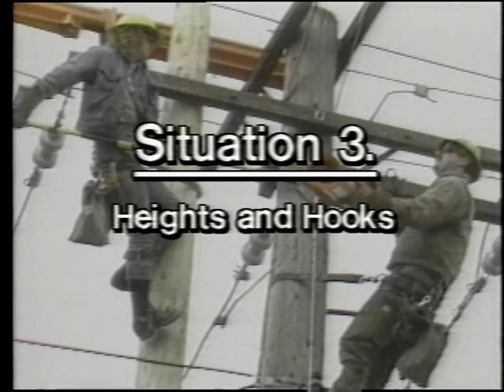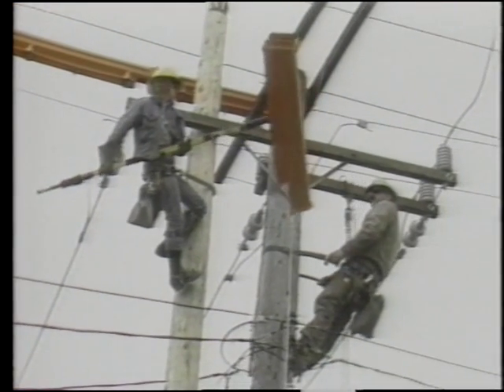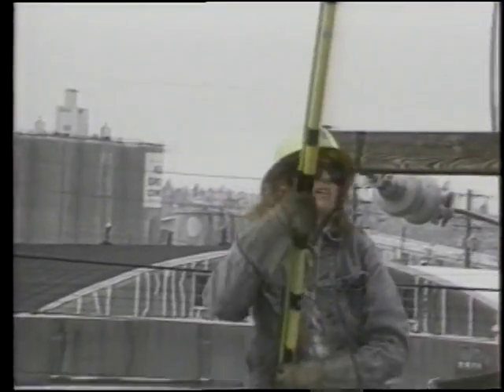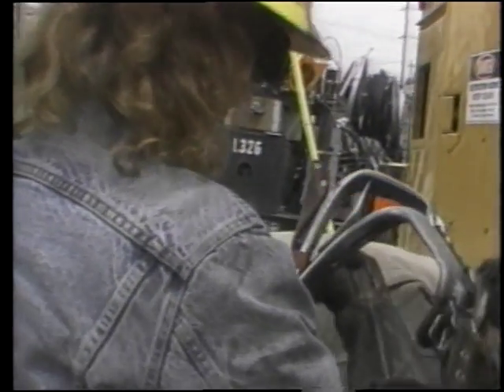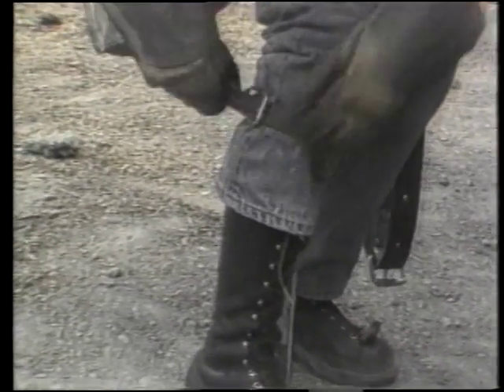Situation three: heights and hooks. We are seeing plastic blankets placed over the energized lines to protect the crew. Plastic or rubberized goods act as insulators — it is an important safety step to put them in place before actual work begins. Hooks are very important to the line worker. They are made of steel and aluminum. A one-and-one-eighth-inch hook, or gaff, protrudes from the instep — it is this hook that the line worker kicks into the pole when climbing. These are worn over specialized high-top line worker boots, then strapped and buckled snugly into place.